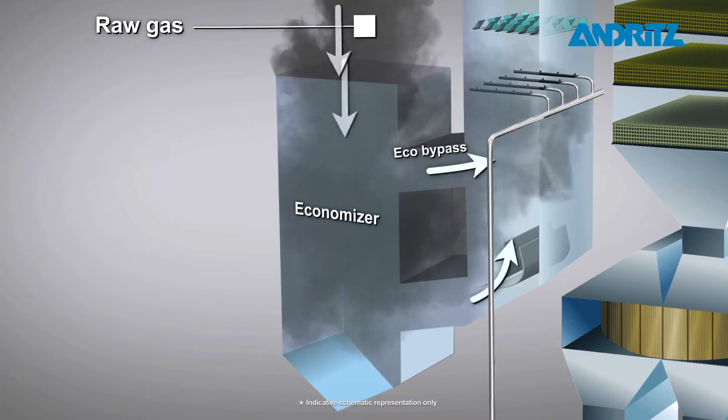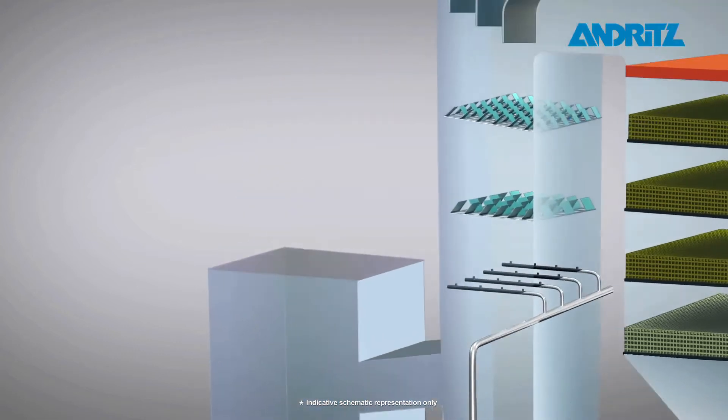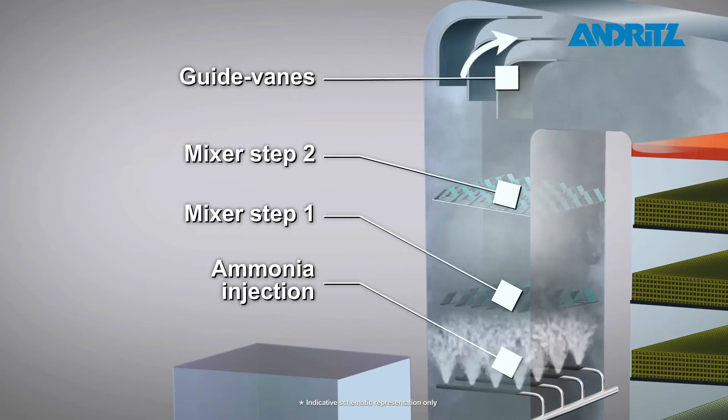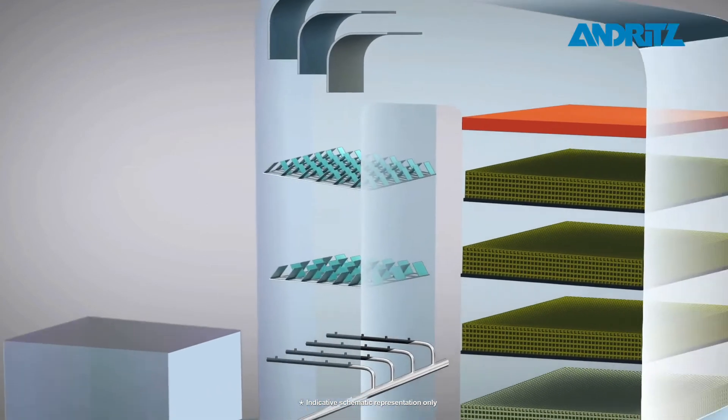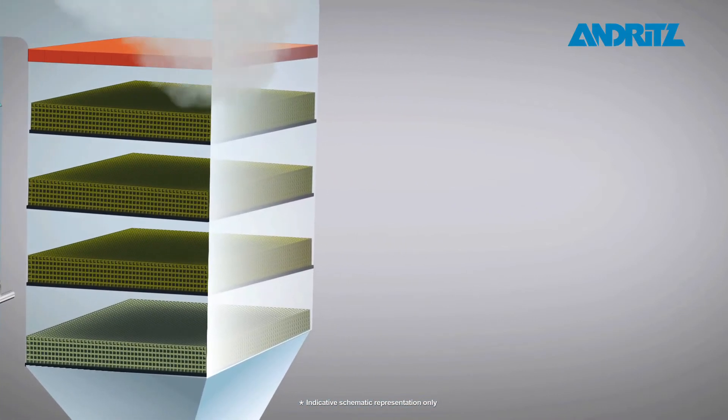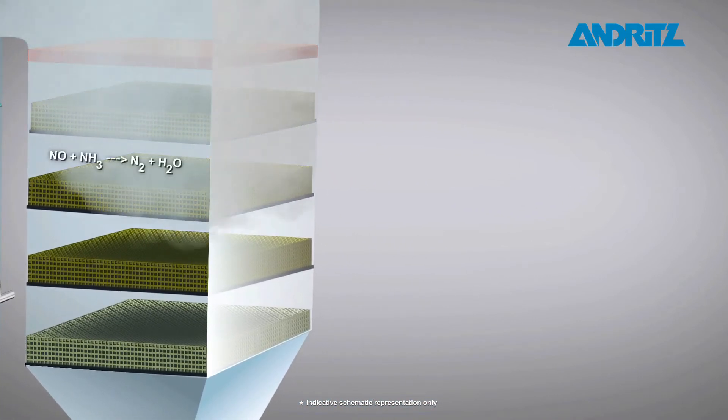The flue gas entering the reactor passes through the ammonia injection grid where ammonia is injected into the flue gas. The gaseous mixture passes through the catalyst where reduction of the oxides of nitrogen takes place.